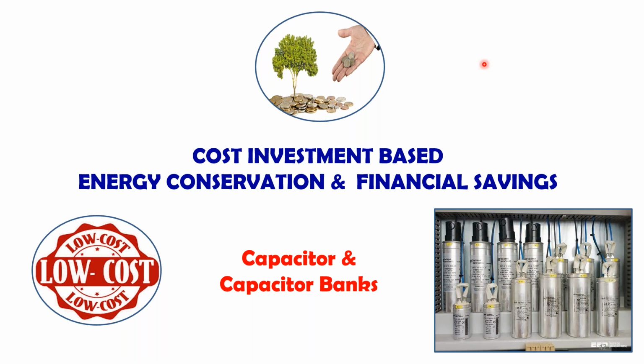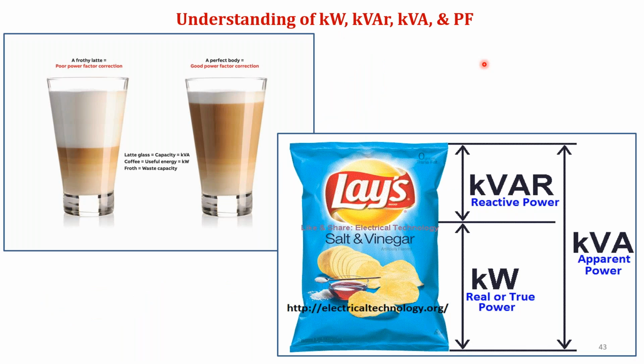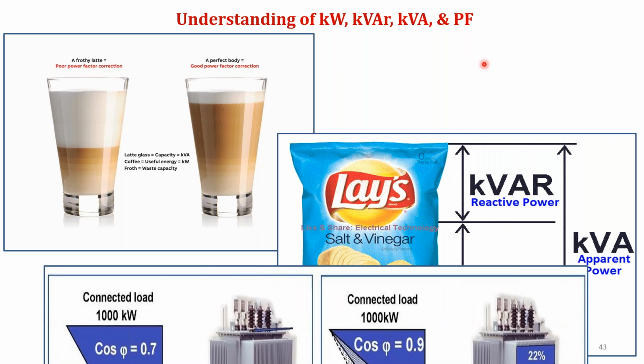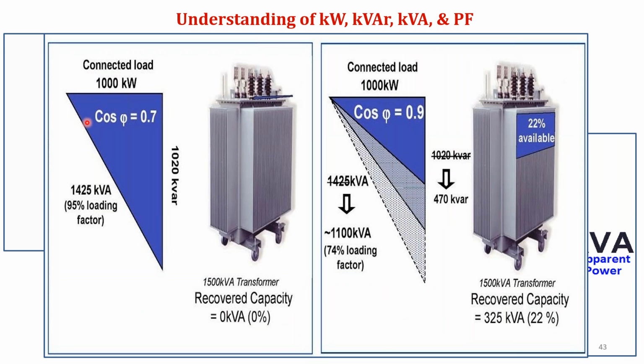So the next one is the capacitor bank. Most of the time we know that the power factor will invite a penalty, and this is the primary slide on how to maintain the kilowatt and kVA. If you are not maintaining the power factor and it is low, then your kVA requirement and the loading capacity will be impacted. If it is boosted from 0.7 to 0.9, then I can increase the loading capacity of my primary equipment from 0% to 22%.